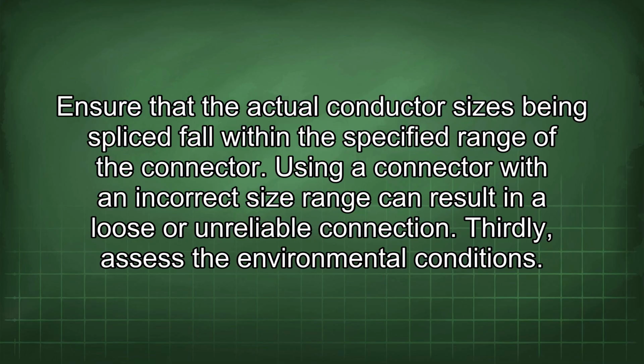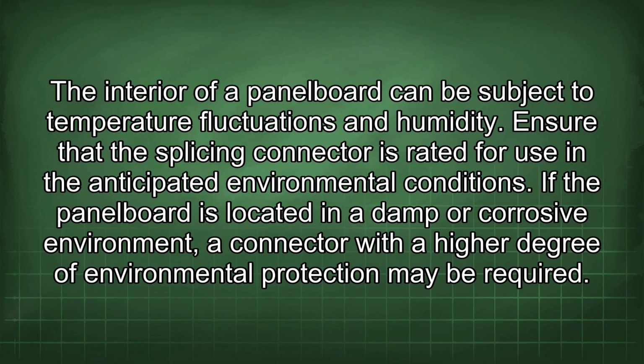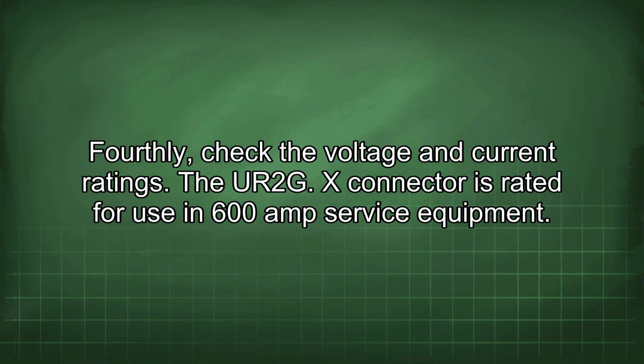Thirdly, assess the environmental conditions. The interior of a panel board can be subject to temperature fluctuations and humidity. Ensure that the splicing connector is rated for use in the anticipated environmental conditions. If the panel board is located in a damp or corrosive environment, a connector with a high degree of environmental protection may be required. Fourthly, check the voltage and current ratings.